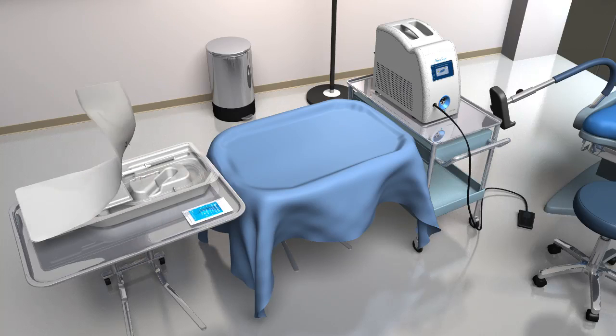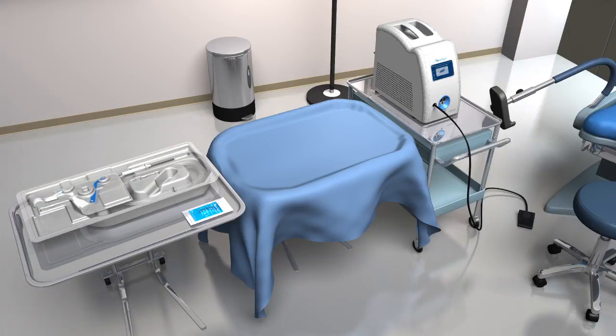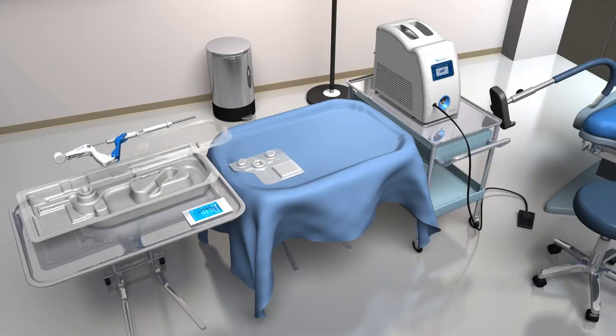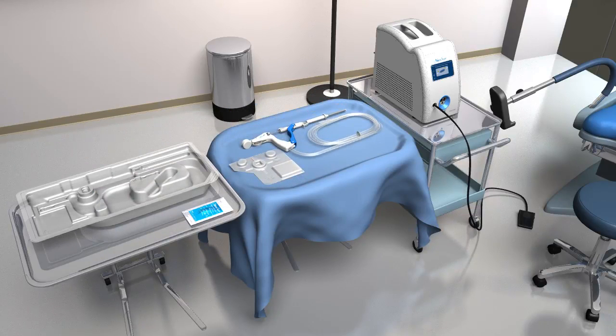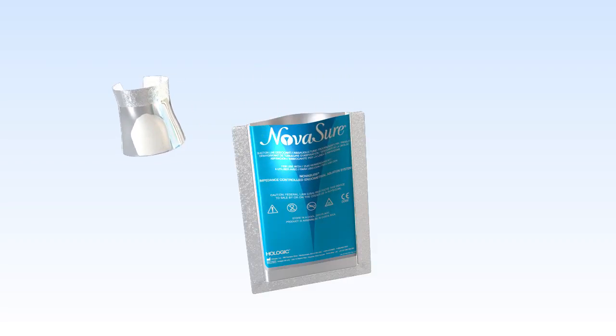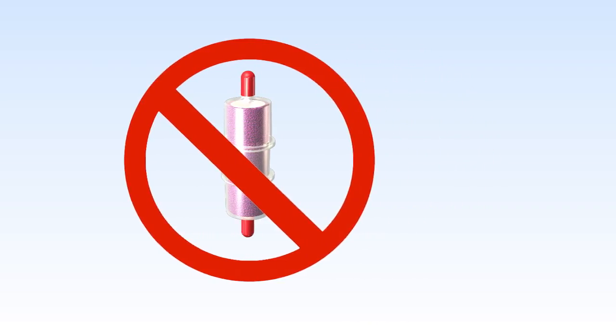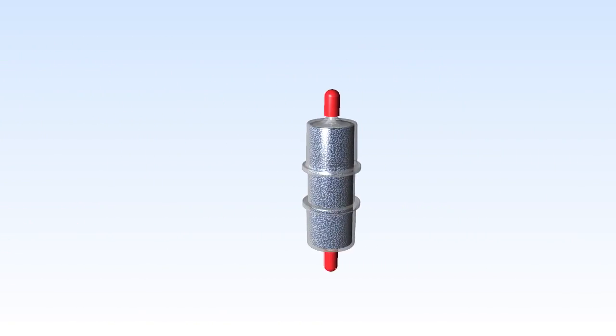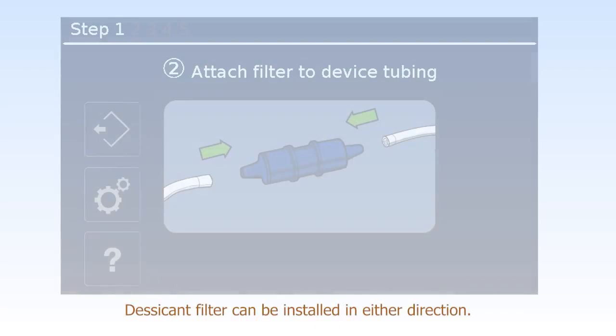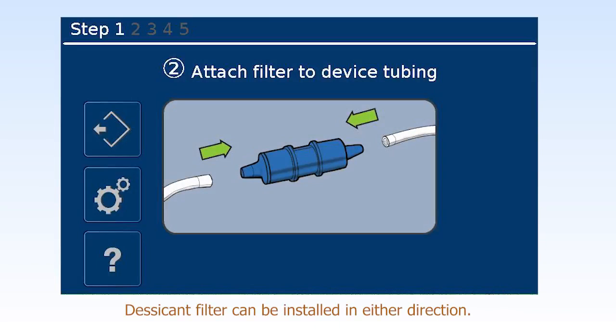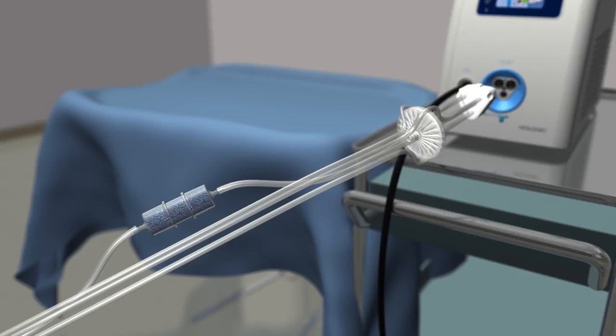Open the sterile NovaSure Advanced device package. Place the disposable device and the connecting cord into the sterile field, while being careful to keep the non-sterile suction line desiccant filter pouch out of the sterile field. Open the non-sterile suction line desiccant pouch. If the suction line desiccant filter is pink, replace the filter prior to initiating the ablation procedure. Remove the protective red caps and connect the desiccant filter barbs into the suction tubing of the disposable device. Ensure both ends of the desiccant filter are fully inserted.